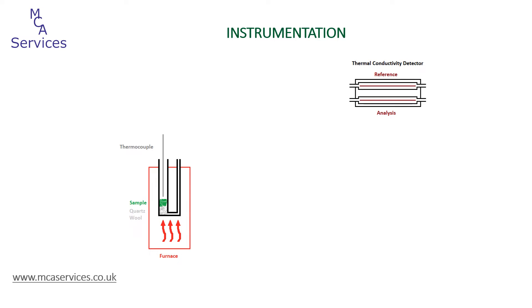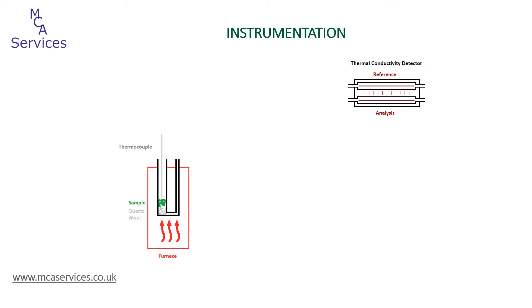Essentially, both sides contain very thin inert wires, usually gold or platinum, and we measure the potential difference across them as the detector signal. The TCD also contains a heater shown here as the red block between the two channels. On the AutoChem, the various zones — for example above the furnace, the detector, and a cold trap zone — are all heated to maintain thermal stability throughout the analysis. It's quite common to heat the TCD block to somewhere between 150 and 200 degrees. The TCD is the really delicate part of the system, and we always have to bear in mind that we need to protect it and not pass materials we don't want reaching it.